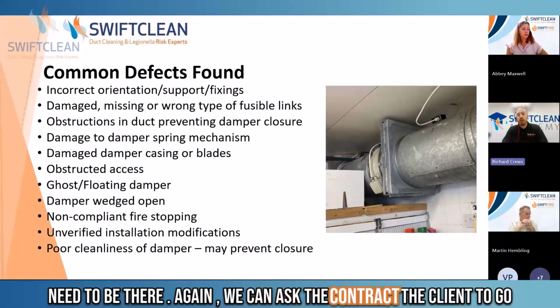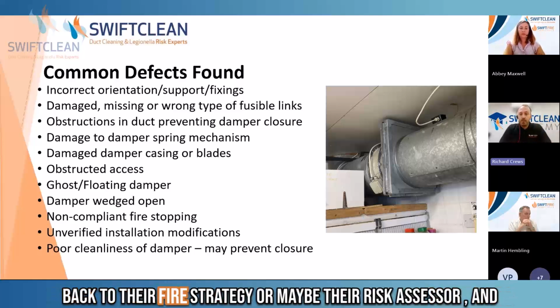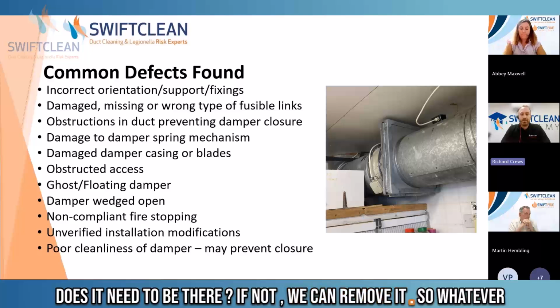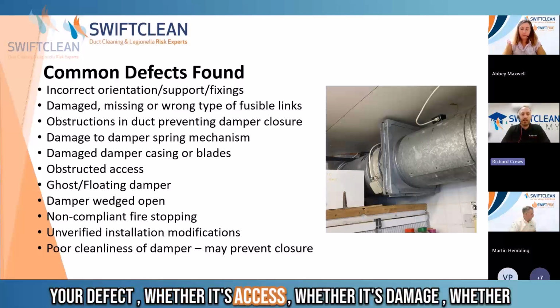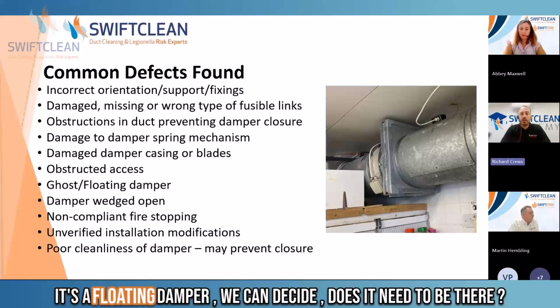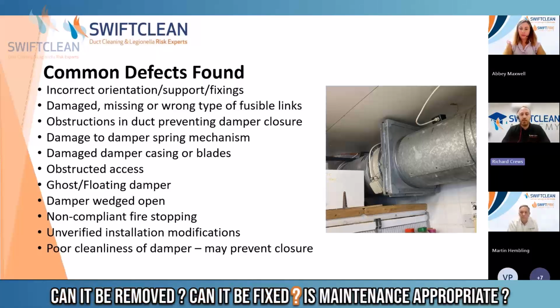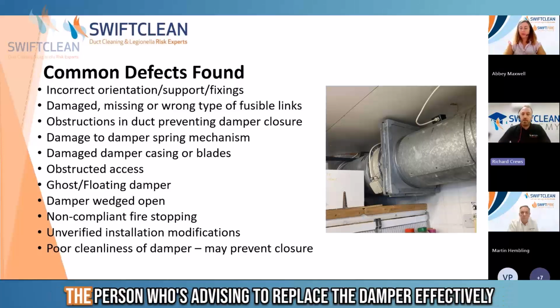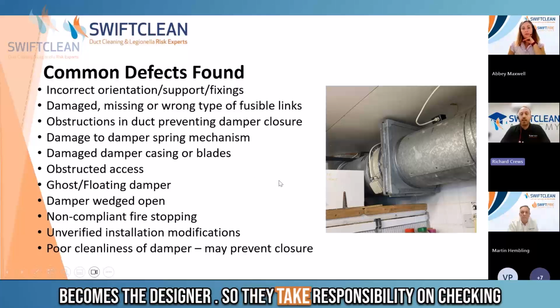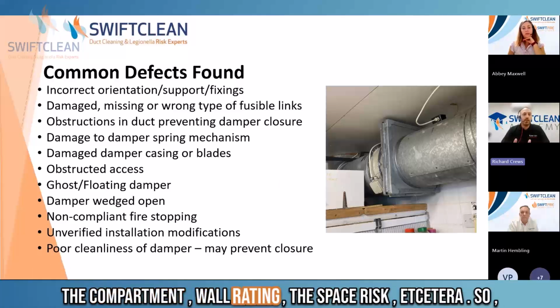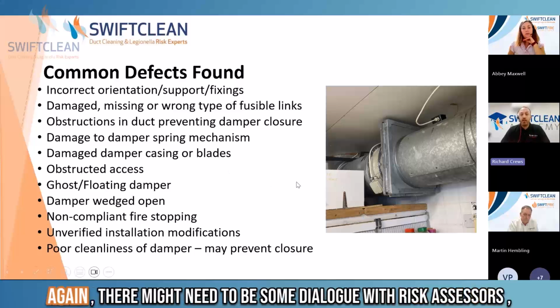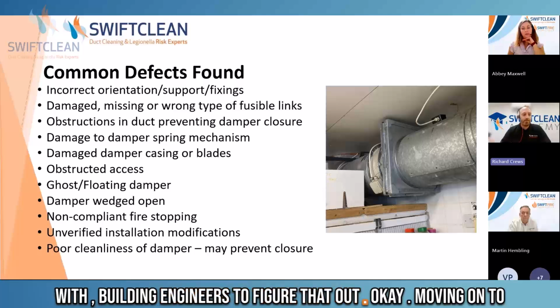Again, we can ask the client to go back to their fire strategy or maybe their risk assessor, and does it need to be there? If not, we can remove it. So whatever your defect, whether it's access, whether it's damage, whether it's a floating damper, we can decide, does it need to be there? Can it be removed? Can it be fixed? Is maintenance appropriate? The person who's advising to replace the damper effectively becomes the designer. So they take responsibility for checking the compartment wall rating, the space risk, etc. So again, there might need to be some dialogue with risk assessors, with building engineers to figure that out.